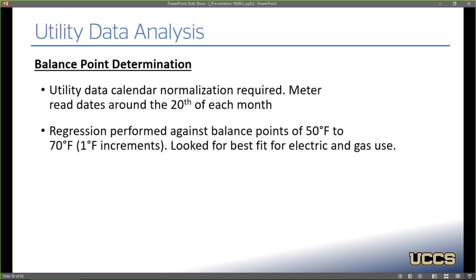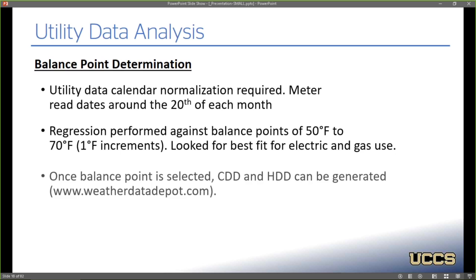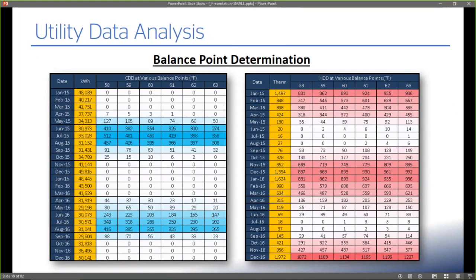So a regression was performed against balance points from 50 to 70 degrees in 1 degree increments, and I looked to see, on both the electric and the gas side, where the data seemed to fit the best. And then once that balance point is selected, I can generate my cooling and heating degree days from weatherdatadepot.com. And here's an excerpt from my balance point determination spreadsheet.